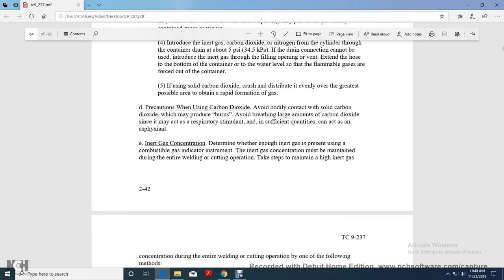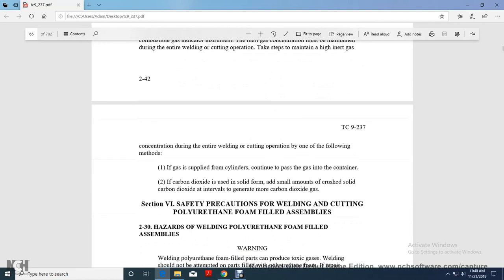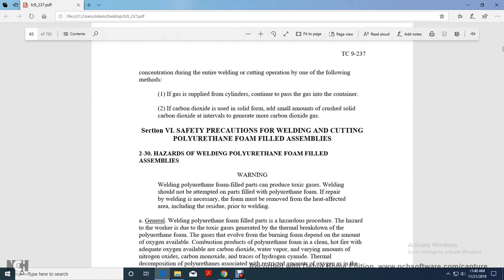Inert gas concentration. Determine that enough inert gas is present using a combustible gas indicator, and maintain the inert gas concentration during the entire welding and cutting operation. Take steps to maintain a high inert gas concentration by one of the following methods. If gas is supplied with a cylinder, continue to pass gas into the container. If carbon dioxide is used in solid form, add small amounts of crushed solid carbon dioxide at intervals.